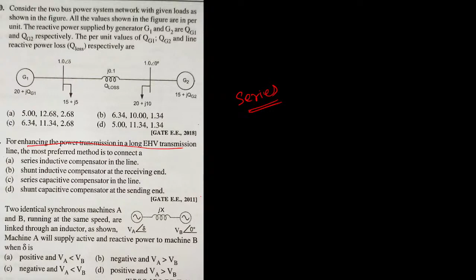For enhancing the power transmission of a long extra high voltage transmission line, the most preferred method is to connect... Which method can we prepare? The best choice is series capacitor compensation. It reduces the line reactance. Then what will happen? Power flow in the transmission line varies, and it will be inversely proportional to reactance X.